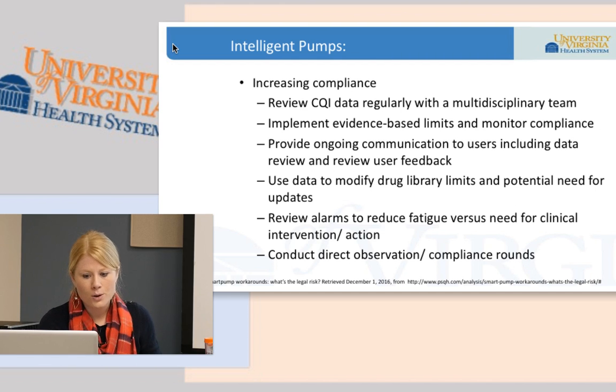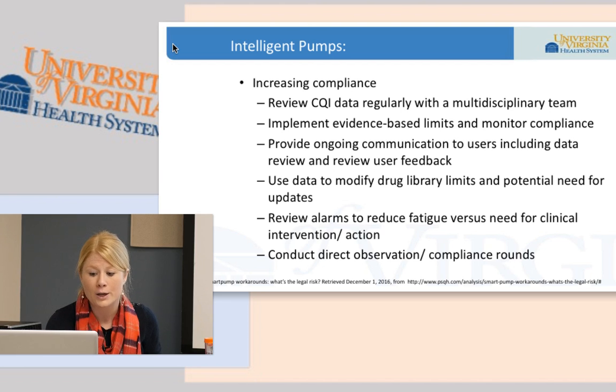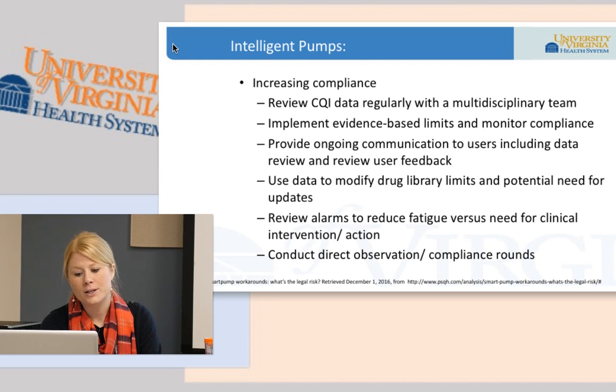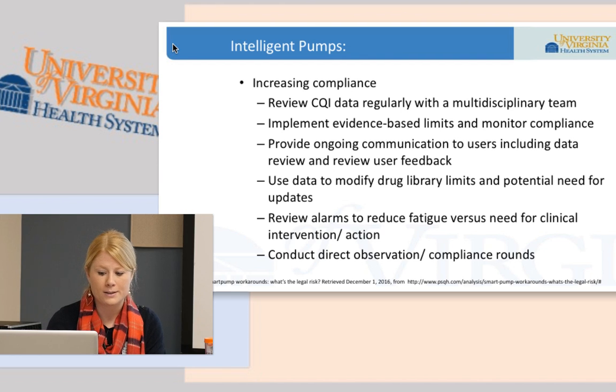So how do we increase compliance with the intelligent pumps? I mentioned that that was imperative for the pumps. Some of the suggestions include reviewing the continuous quality improvement data regularly with a multidisciplinary team. Implement evidence-based limits and monitor compliance, so that ties together as well. Provide ongoing communication to users, including data review and user feedback. Use data to modify drug library limits and identify potential need for updates. Review the alarms to reduce fatigue versus need for clinical intervention and action. So we talked about the importance of that balance earlier. And conducting direct observational or compliance rounds is also recommended to enhance intelligent pump user safety.